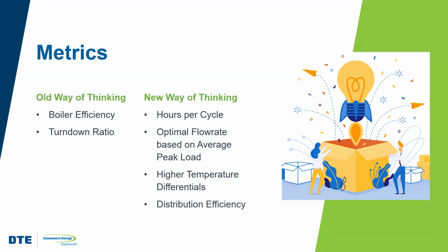In terms of the boilers, right? The old way of thinking was looking at really the boiler efficiency and the boiler turn down, looking at the piece of equipment itself, right? Our new way of thinking, right? We want to look at things like the hours per cycle that the boiler is operating. We want to look at the optimal flow rate for the boiler. We want to look at higher temperature differentials for that boiler. And we want to look at distribution efficiency. So we want to begin thinking about other things as opposed to just the boiler's turn down and just the boiler efficiency. When we look at the overall system performance, right?